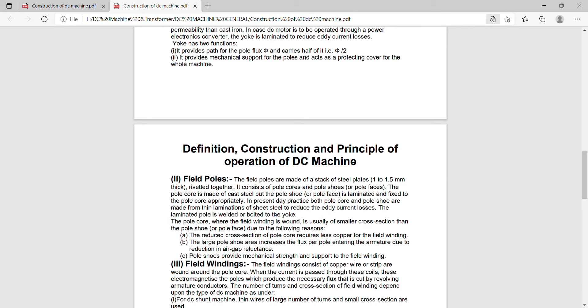In present day practice, both pole core and pole shoe are made from thin lamination of steel to reduce the eddy current losses. The pole core where the field winding is wound is usually of smaller cross section than the pole shoe.